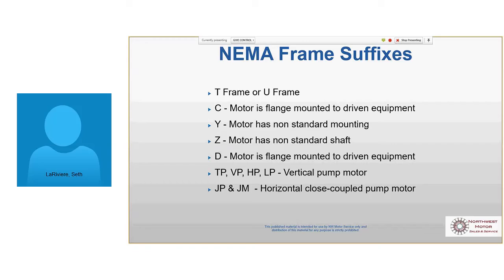And a lot of them are designed to hold the extra weight of the driven equipment. They have thrust bearings on them because a lot of pumps will pull down. The impeller design pulls down on the rotor or pushes up on the rotor, depending on which way it's running and what the pitch of the blade is. So you've got a lot of additional stuff going on in vertical motors.